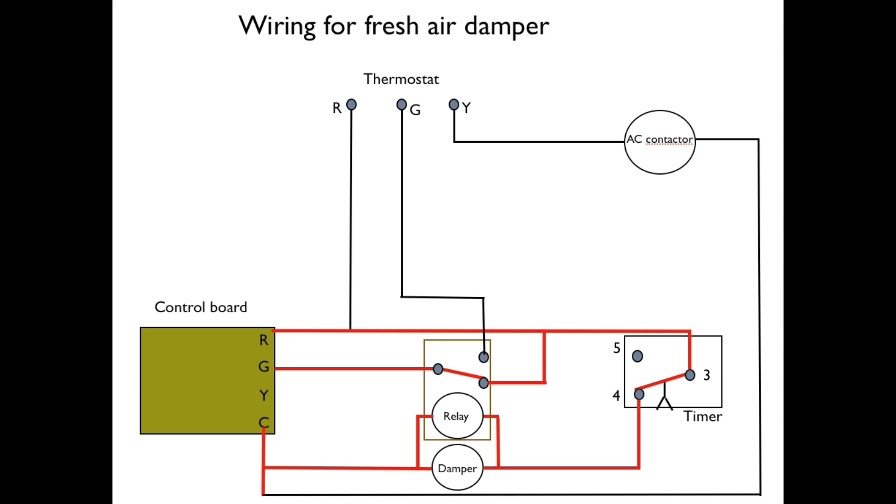So that's pretty much it. There's more to it if you put the exhaust fan in and the fans and all this, but this is basically how it works. And if you get this thing put in backwards or you don't consider that fan going through the thermostat, you will end up with the air conditioner turning on when the outside air damper comes on. Hope this one helps.